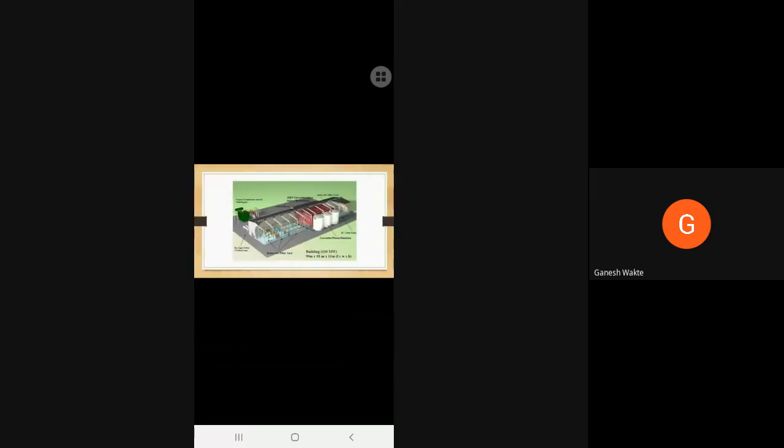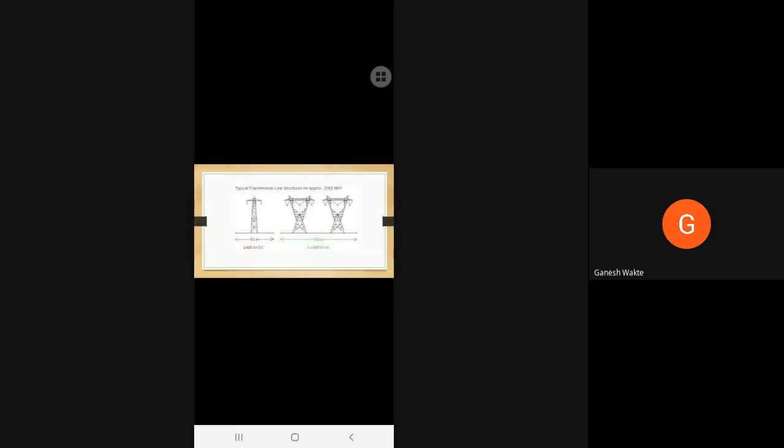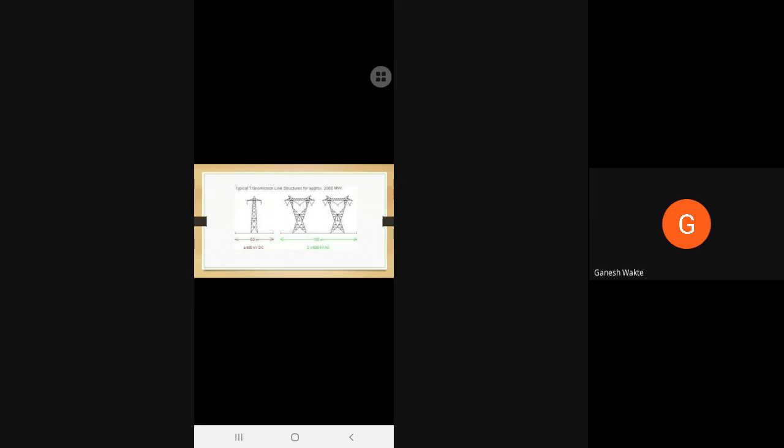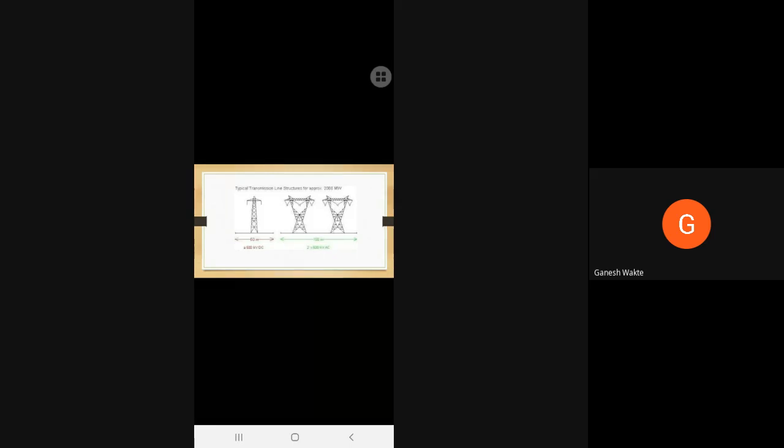Let us discuss here the typical view of the HVDC. In HVDC you can see there is a converter IGBT wall, then reactor, DC yard, AC yard. This is everything in the converter stations. You can see here the advantages of using DC line: to transmit 200 megawatt power from AC line we require two towers and two transmission lines, but for HVDC we require only one tower and less space.